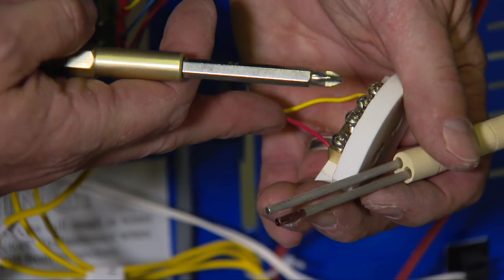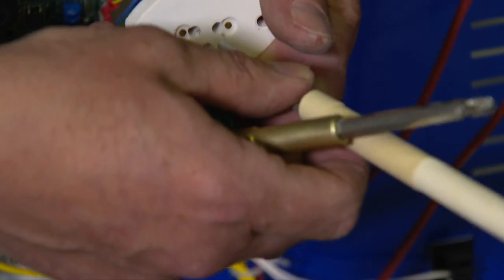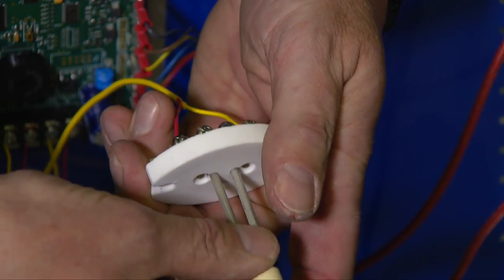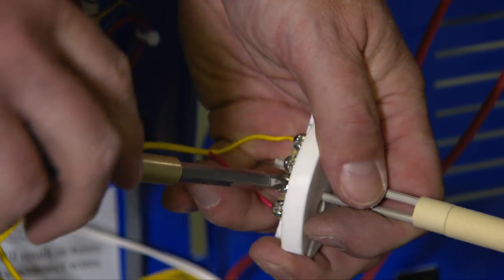Take your new thermocouple, noticing that there's a red painted tip that needs to line up with the red wire on the thermocouple block. Put it in place and secure the two Phillips screws.